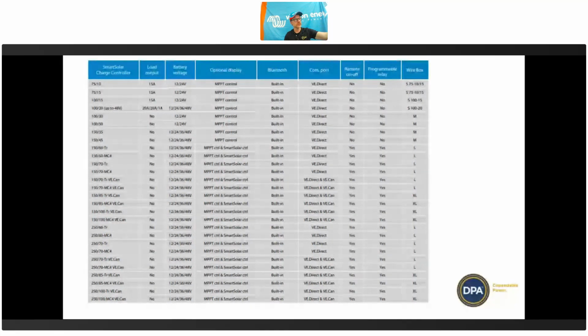So this one, the first one here, 7510, you can put an open circuit voltage of up to 75 volts into that. And then the second value is the maximum current that it will put out. Now, because the input voltage is 75, that means it's basically only suitable for 12 and 24 volt battery systems. If you want to charge a 48 volt battery system, you have to go down the range here until you get to an input voltage of 150. So you've got enough voltage headroom to charge a 48 volt battery.